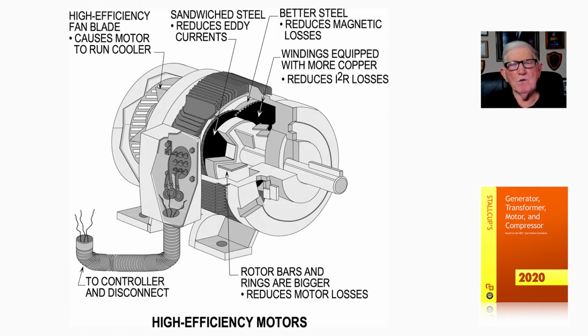So same thing with a motor. If you lower the impedance and everything of the motor, it's going to have more inrush current. And that's why the National Electrical Code in 430.52(C)(3) and the exception would allow you to go up to as high as 1,700% to allow high efficiency motors to start that could draw up as high as 15 times.